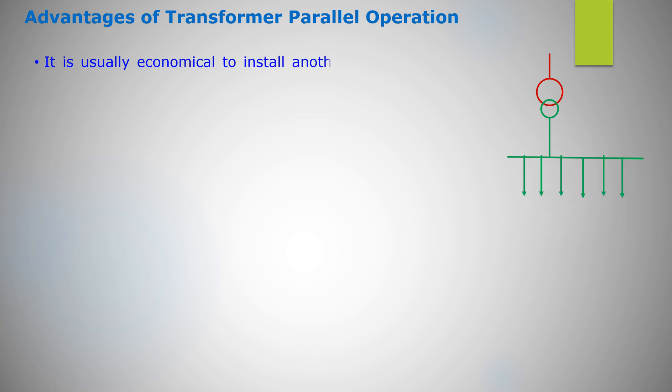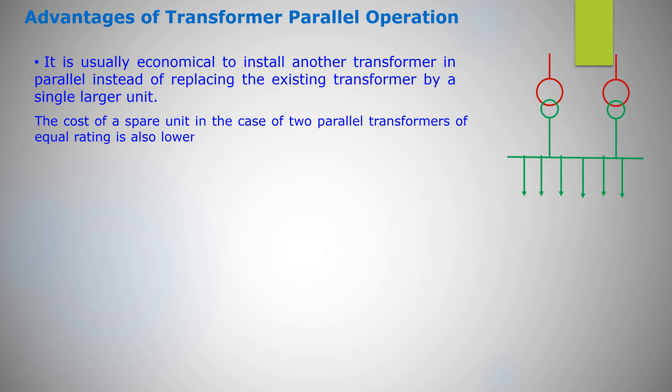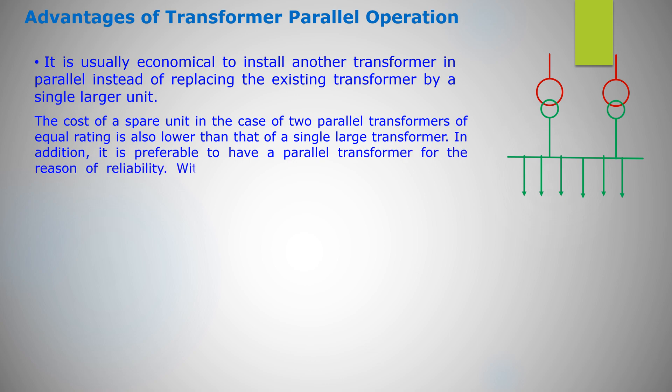Advantages of transformer parallel operation: It is usually economical to install another transformer in parallel instead of replacing the existing transformer by a single large unit. The cost of a spare unit in the case of two parallel transformers of equal rating is also lower than that of a single large transformer. In addition, it is preferable to have a parallel transformer for the reason of reliability. With this, at least half of the load can be supplied with one transformer out of service.